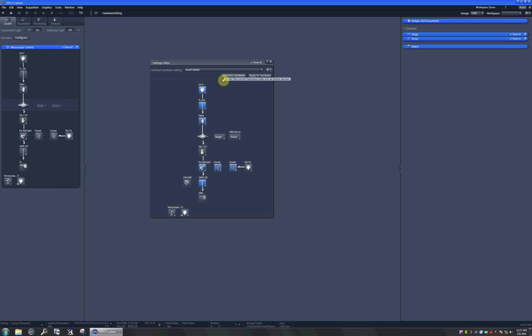And you can do the same for fluorescent channels as well. When you're using a fluorescent channel, you don't want any transmitted light, and you want a lot of light from the mercury lamp. And it's best to close the shutter here. And you don't care if the lamp is on or off, because the shutter is closed, so you can just exclude it from the setting.